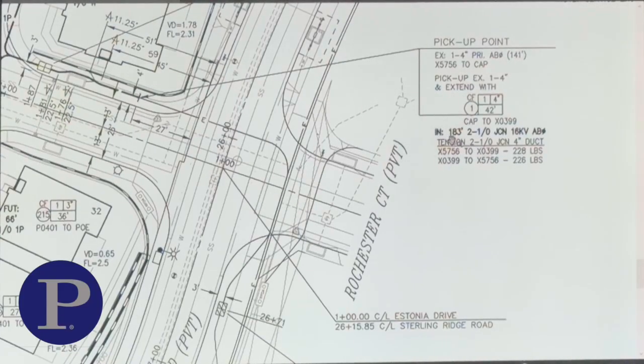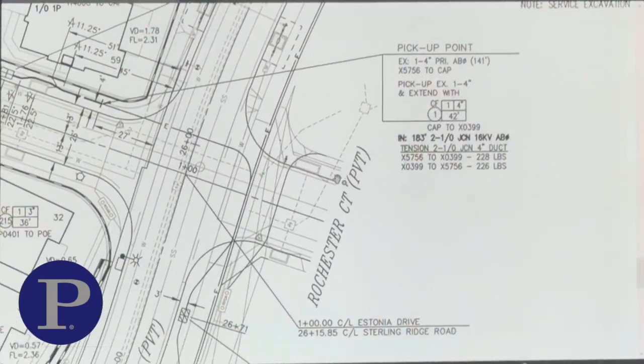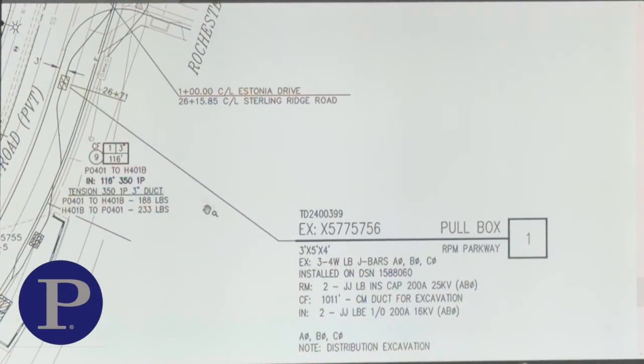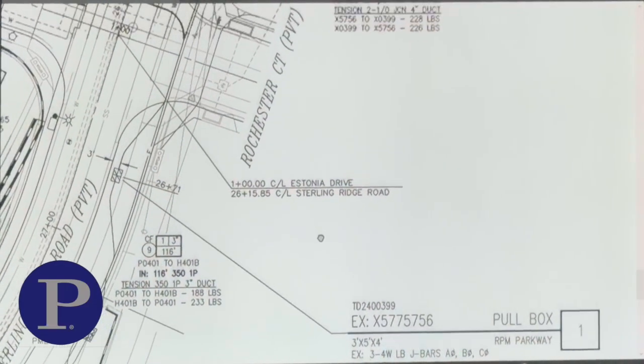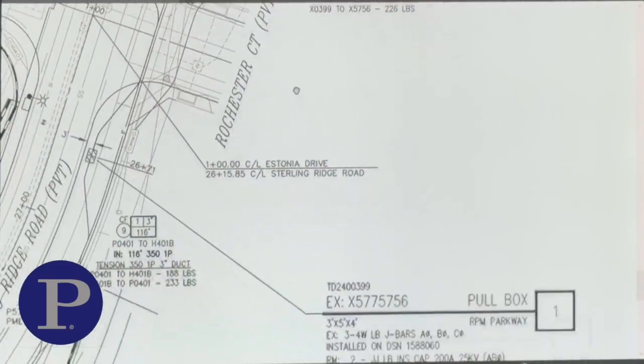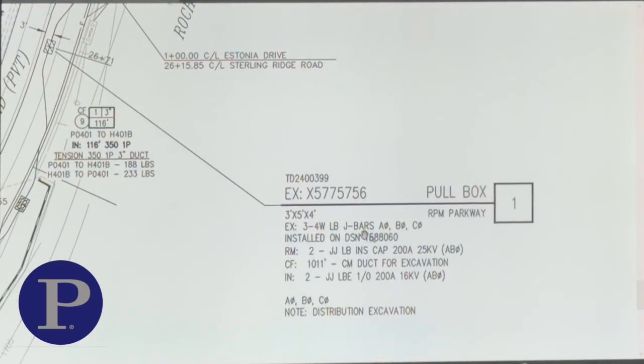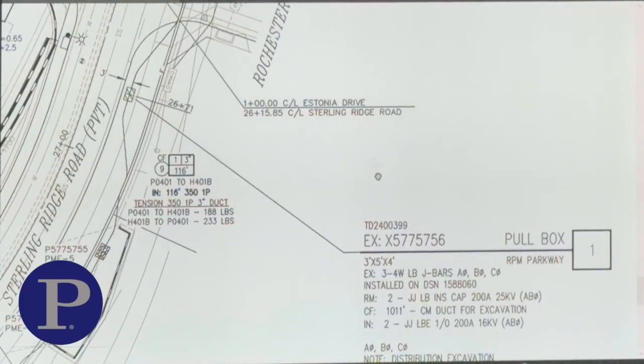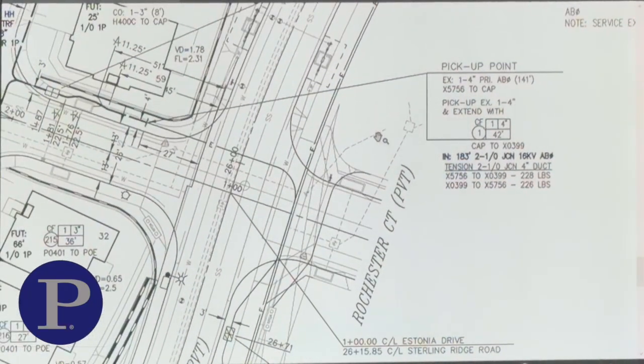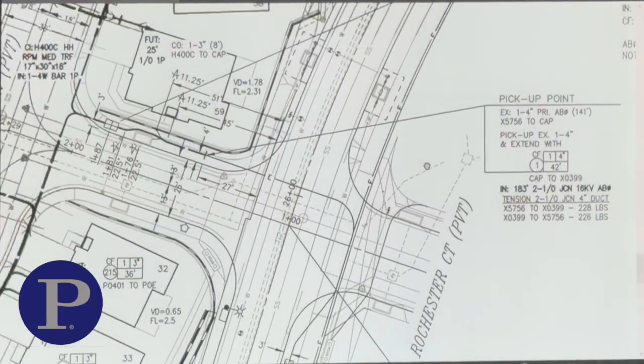It'll give us the footage at 183 feet. It'll give us 2 conductor 1-aught. That's the type of primary cable that we're pulling, JCN, and this will show you the phase marking. So we're going to mark this A and B. So this pull box right here has 3 junction bars in it, A, B, and C. When we're pulling off a single phase system with 16 kV, we're going to use 2 of those conductors, and it could be AB, it could be BC, could be AC, could be any one of those different configurations. But we know from this we're going to be AB phase on the primary.